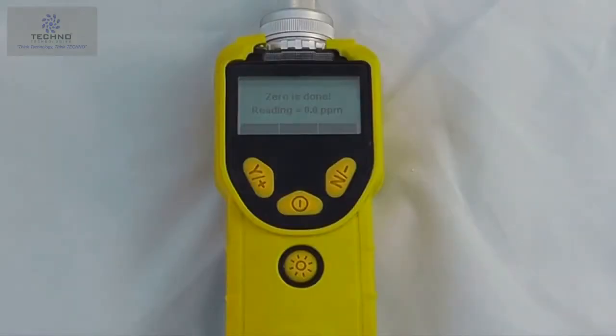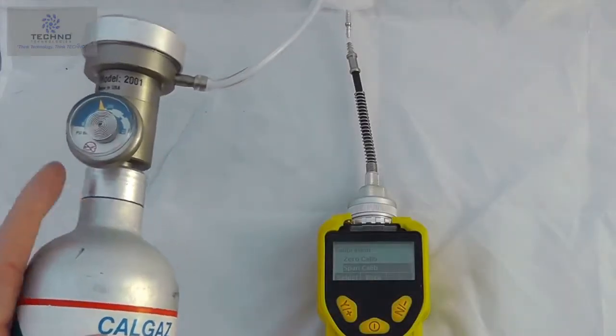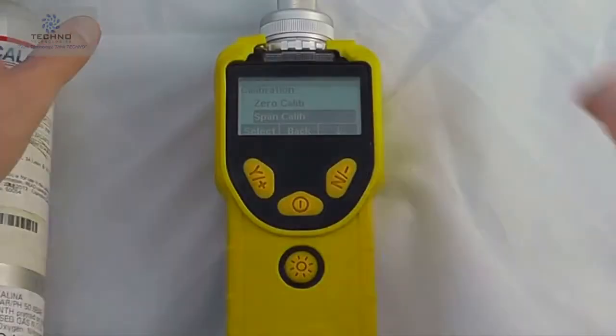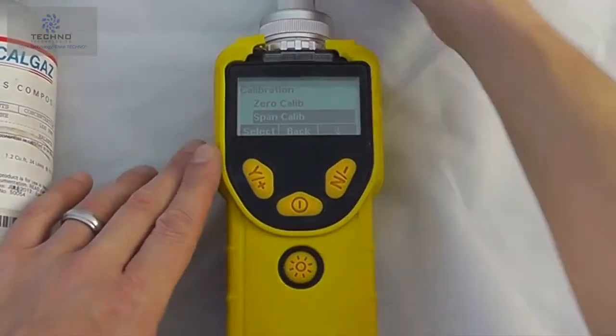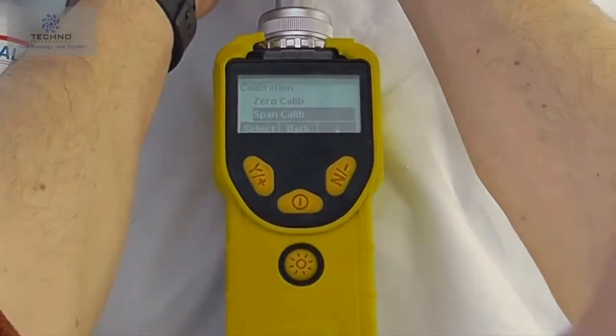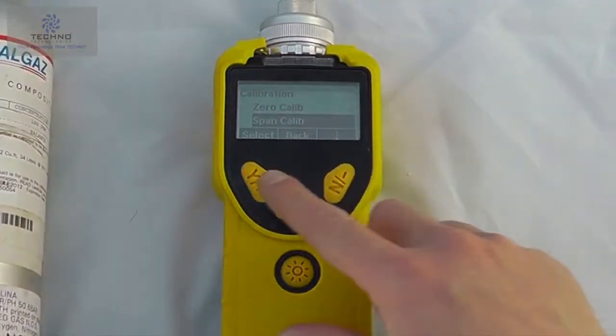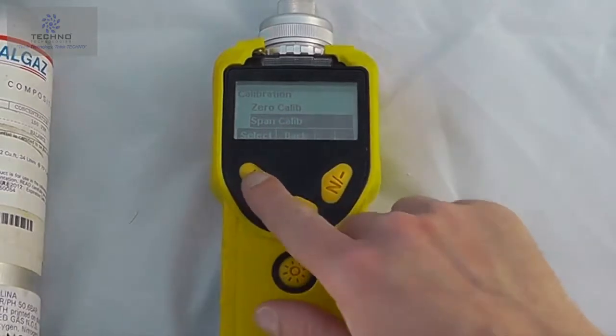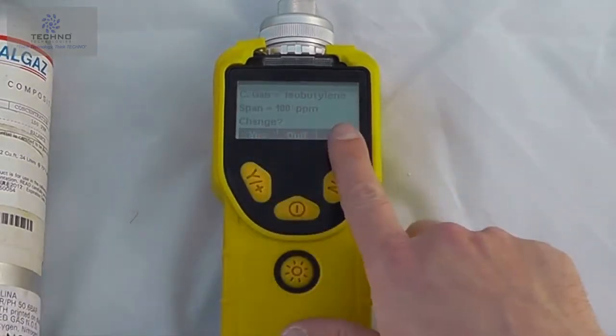So that 0 reading has now been successful. So we've set our point 1 of our 2-point calibration. We then get an option to span calibrate the device. So for our purposes here, I'm going to use a can of isobutylene with an on-demand regulator. So if we place that over the unit, we can remove the hydrophobic filter from the top of the instrument. Then if we select span calibration, it'll ask us to apply the gas.